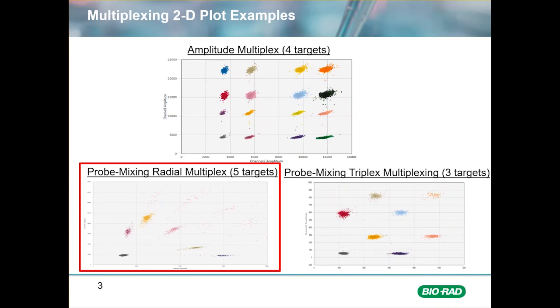Here are three examples of ddPCR multiplexing strategies and how the clusters might appear on the 2D plot. At the top is an amplitude multiplex with four assays, a probe mixing triplex on the bottom right, and on the bottom left a probe mixing radial multiplex showing a fiveplex. More clusters can be added for further multiplexing. Today we will explore the probe mixing radial multiplexing strategy.